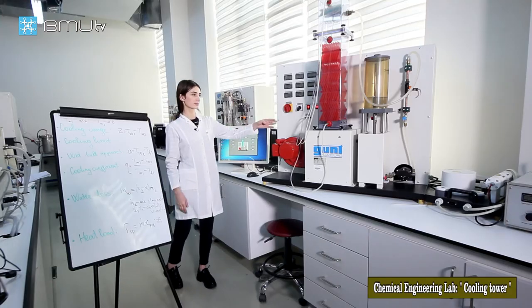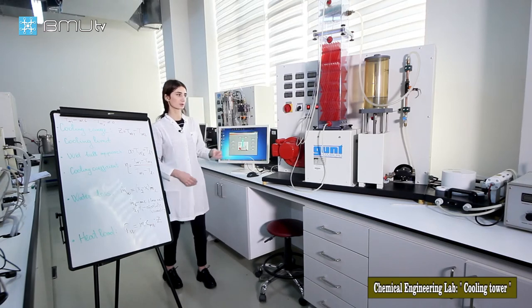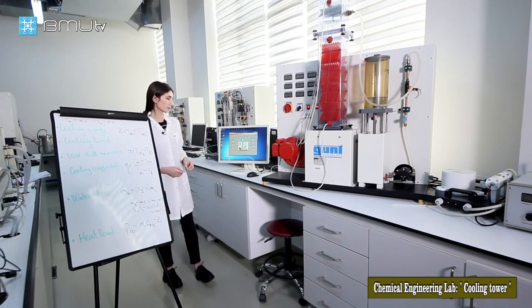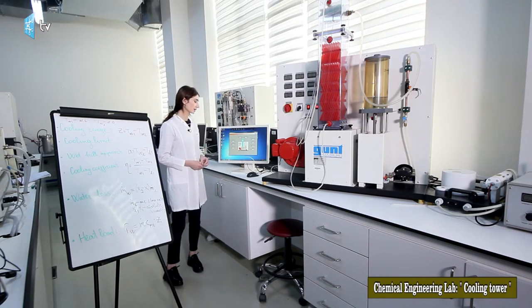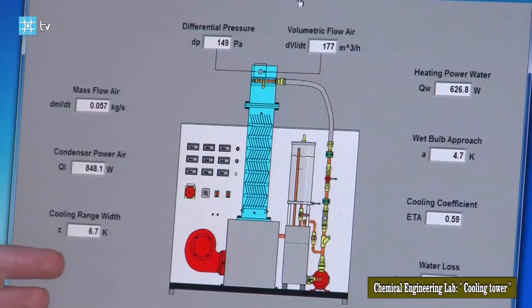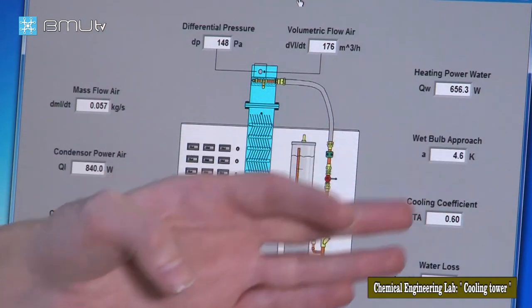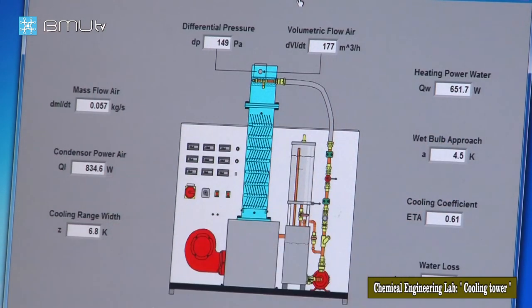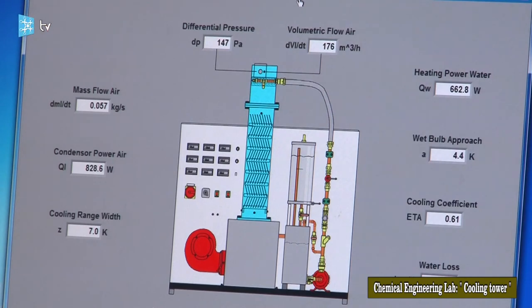We set the heating level of the heater to 2 kilowatts and monitor the results. With increasing cooling water temperature, the cooling range gradually increases, the wet bulb approach decreases, and the cooling coefficient increases. So, increasing the temperature of the cooling water enhances the performance of cooling in the cooling tower.